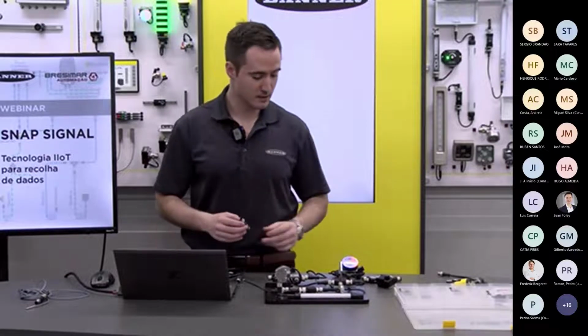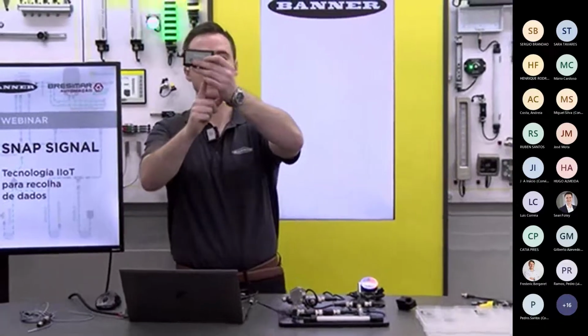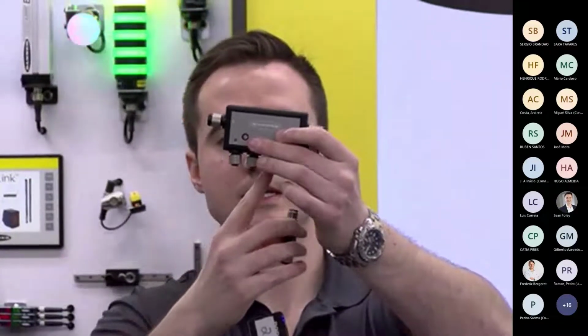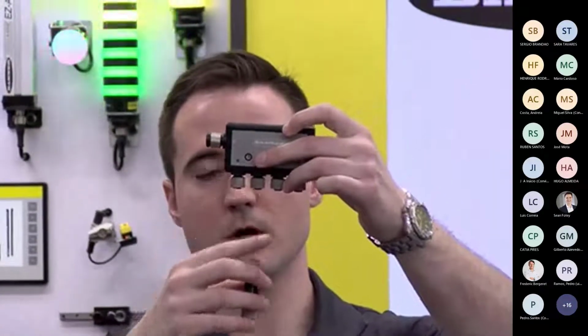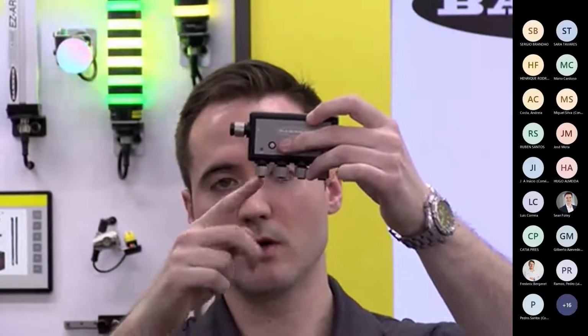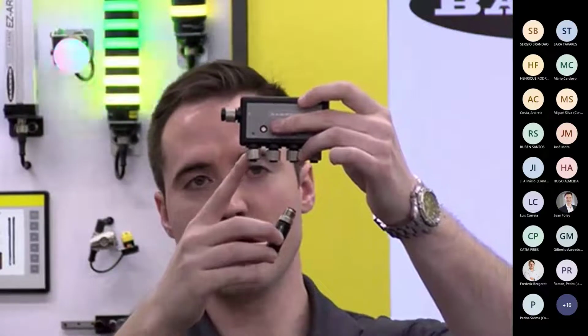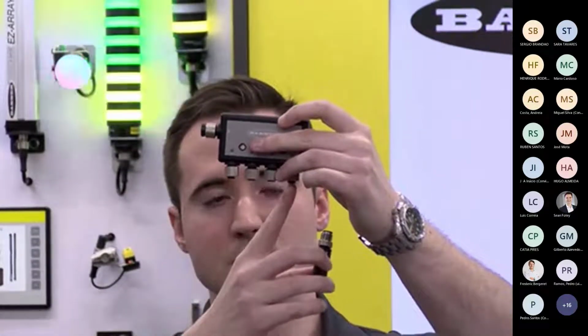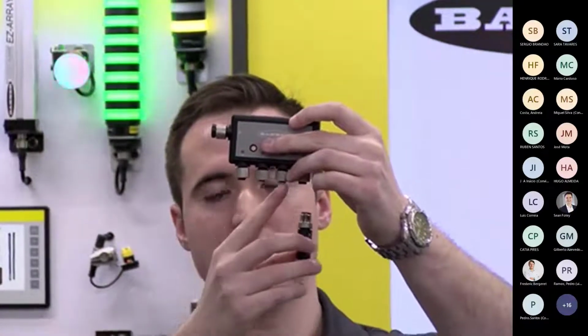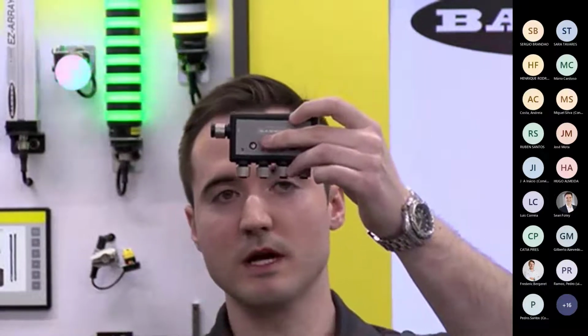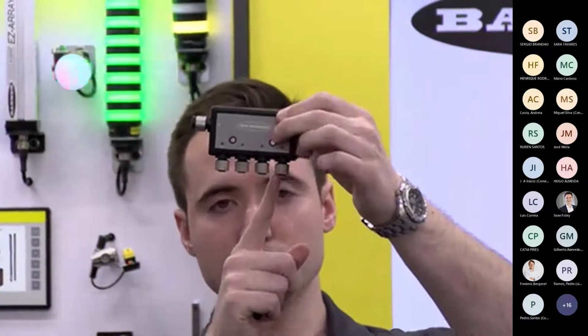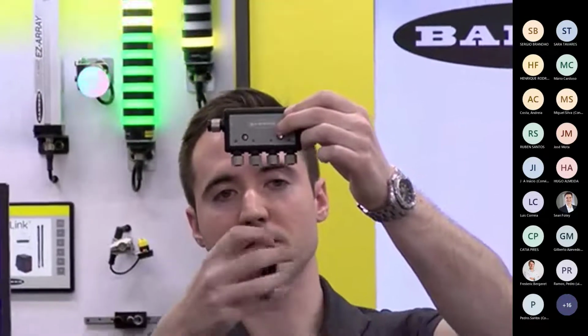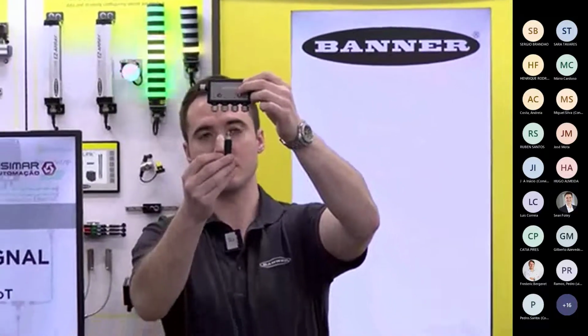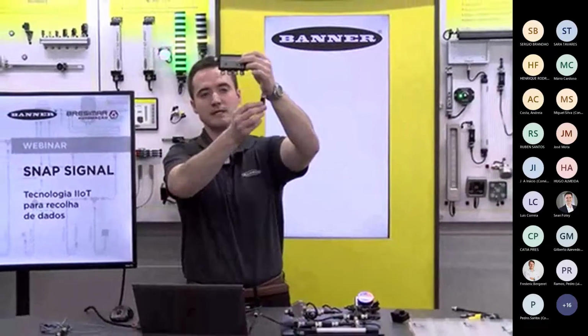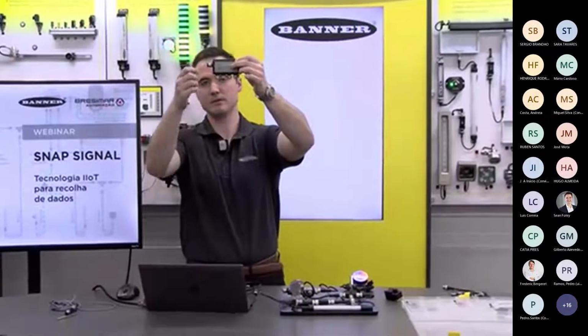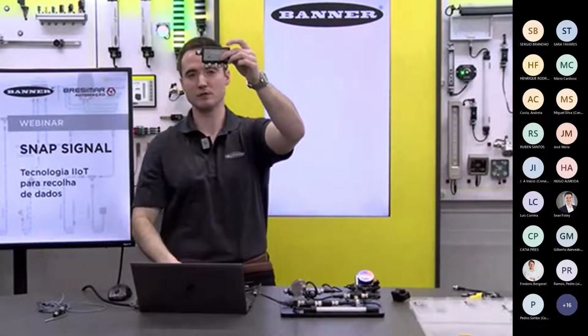One more thing to highlight: each port on this DXM R90 Industrial Controller is an independent network, so you could have large numbers of converters or devices connected on a single port. What's important is that out of the box, each converter is ID 1. Since these are independent networks, you could plug a converter with device ID 1 into each port. But if you have multiple converters on a single port, each of those converters' IDs has to be separate, it can't stay at device ID 1. So you need converters with device ID 1, 2, 3, however many you need. Other than that, that's essentially how you'd avoid issues there.